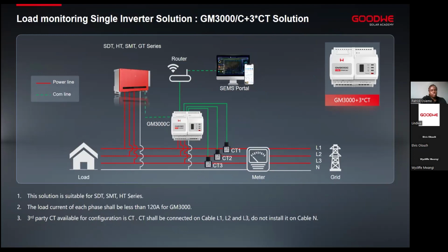In case you're doing a single installation, then yes, this is possible and it's quite simple. You can utilize the GM, GoodWe's own smart meter. We have 2 kinds of smart meters. The GM 3000 will come with CT clamp meters. So in case your AC cable current rating is below 120 amps, then the GM 3000 smart meter will be applicable. If the incomer of the grid has a higher rating or has a bigger sized cable, then the GM 3000C is applicable. The reason being the GM 3000C can work with third-party CTs. So you can connect the 5 amp secondary rated CT to this smart meter and link this smart meter directly to the inverter, and you'll be able to control your export, control zero export, control your plant.